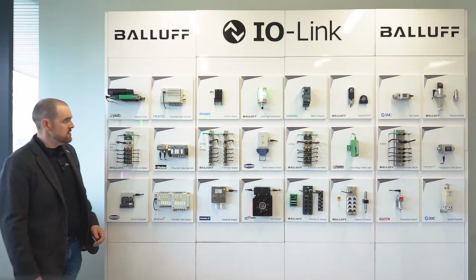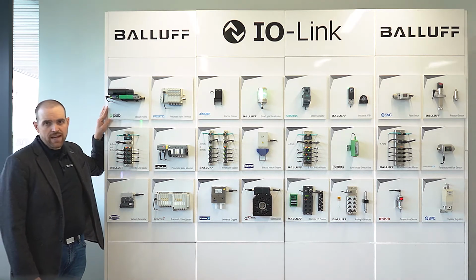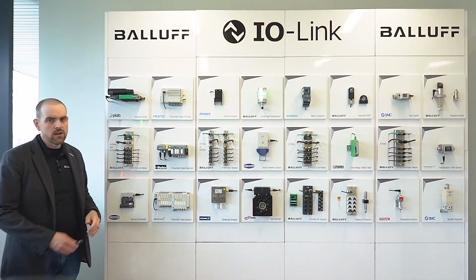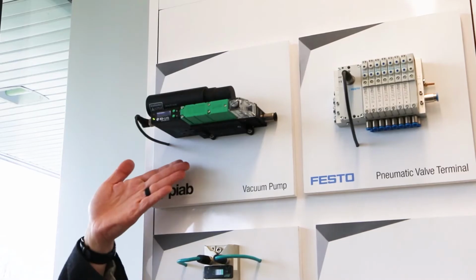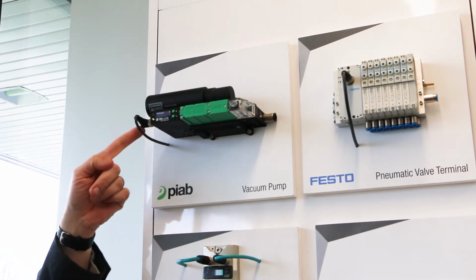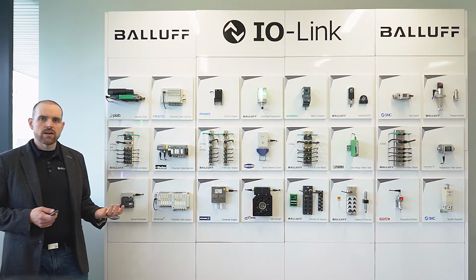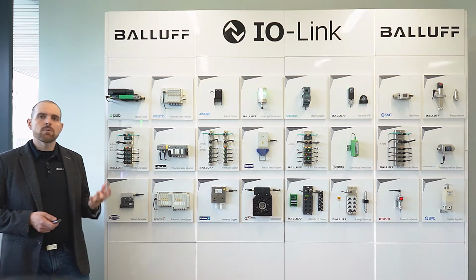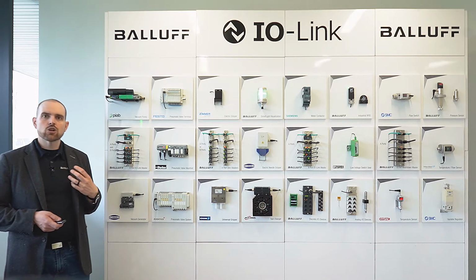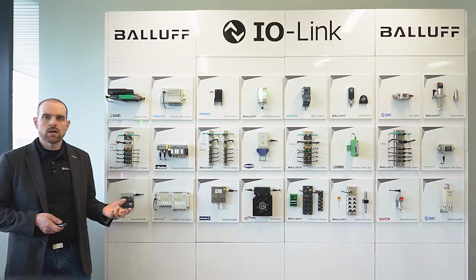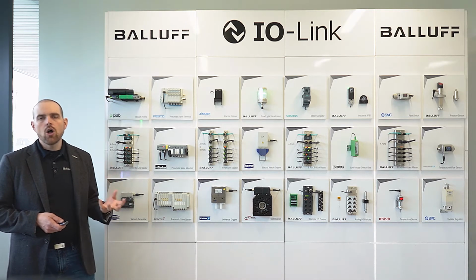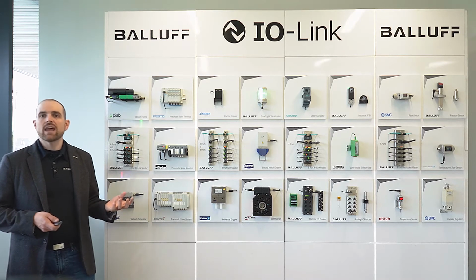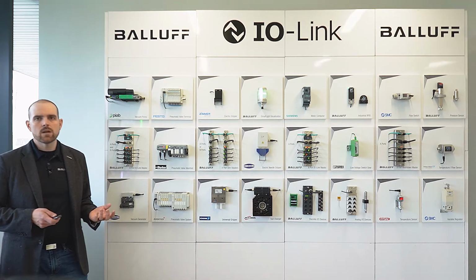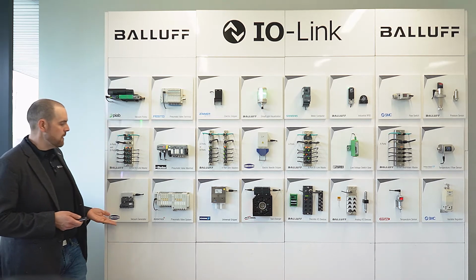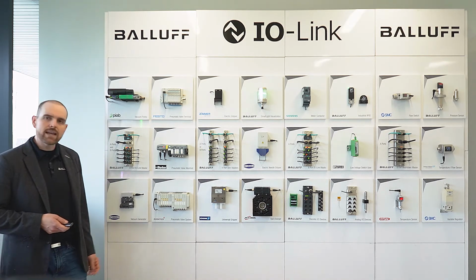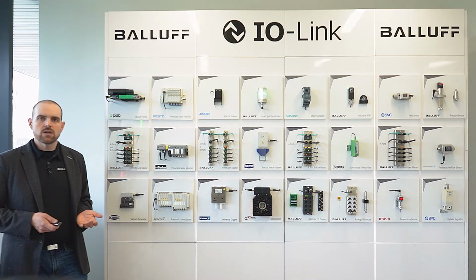The first, you see here, we have two different types of vacuum. I have a vacuum pump and a vacuum generator here, one from Schmalz and one from Piab. These two IO-Link devices are not only vacuum generators or vacuum pumps, but they actually provide diagnostic information and allow you to control the vacuum pressure and these kinds of things, all with the device over IO-Link. So they have parameters as well as process data, and you can control the vacuum pump and get diagnostics from the vacuum generator right over the IO-Link communication.